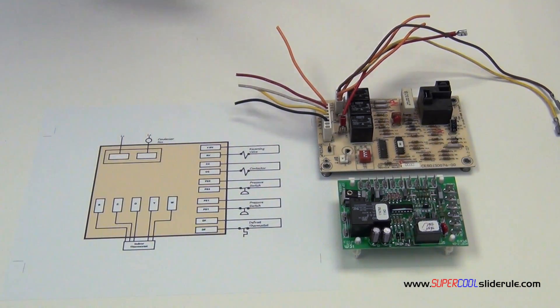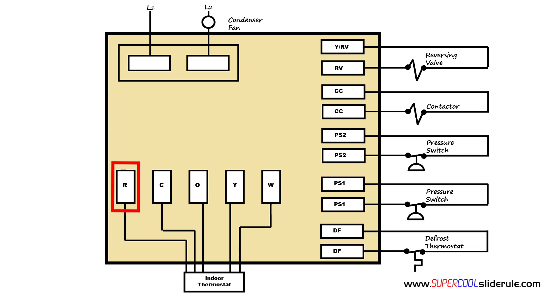The R is going to be our 24 volts that is supplied to the defrost board at all times. C is our common, O controls the operation of the reversing valve, Y controls the operation of the compressor contactor, and W is a terminal that is energized whenever the unit goes into a defrost. It turns on the emergency heat inside.